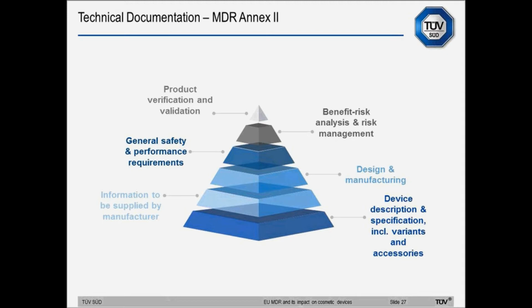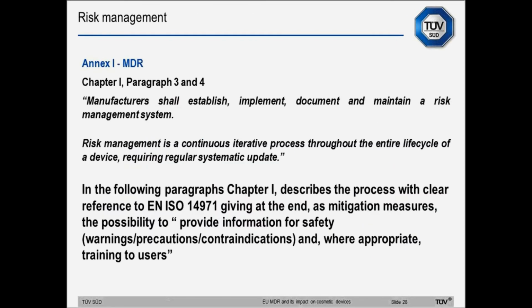After that, you need to identify clear information to be supplied by the manufacturer to the customers or to the users. You need to describe the design and the manufacturing process with certain precision, in order to ensure suitability of those processes. You need to challenge the product against the general safety and performance requirements, producing a checklist for that. You need to verify the benefit-risk analysis and the risk management. At the end, of course, you need to have a product verification and validation that is part of the design process. And now it's time to hand over the speaker's role back to Melania.